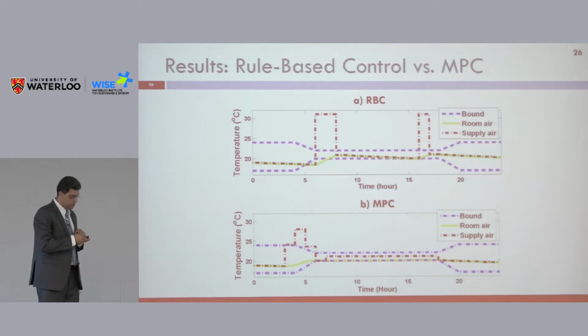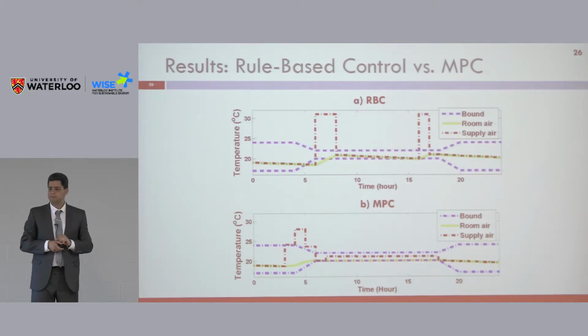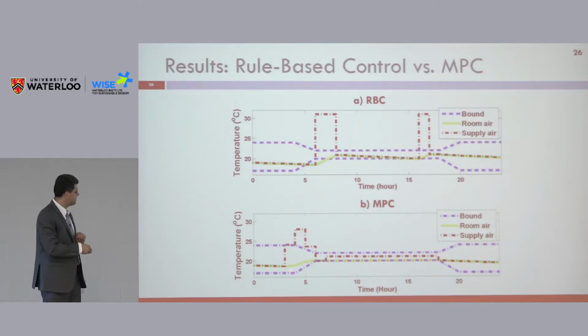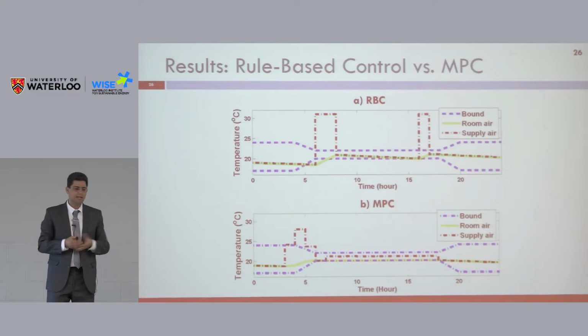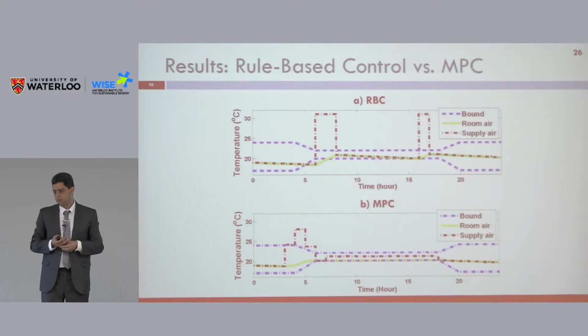In the model predictive control, what it does is say, okay, I'm going to start heating the room earlier. You see this one starting here, say around 3 a.m. — so I'm going to start it earlier. Then the room will be adjusted, always staying within here. What will happen is my room temperature will always be at the lowest bound. So if it's always at that lowest bound that I'm allowed, my energy consumption will become less.